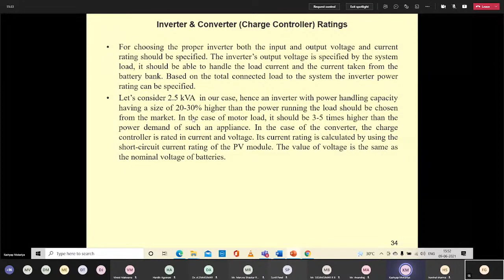For charge controller sizing, I am taking one example, both for EV and for domestic load. The charge controller rating should be 125% of the photovoltaic panel short circuit current. In other words, it should be 25% greater than the short circuit current of the solar panel. In the subsequent slide, I have shown where to get the ISC data.